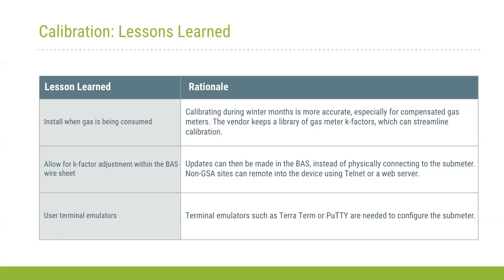As Sean said, this is also used for water uses, and it's easy to have some water usage and calibrate it. But it was harder for us in Texas to actually get this calibrated initially because we didn't have any gas consumption in the building. And there was a difference we found too, and the meter that we used at both sites were compensated gas meters. So it was better to use this in peak heating season whenever we had a constant flow of gas, just to make sure that we got the best calibration possible and to lower the delta that we were seeing between the actual meter readings and what the device was telling us.